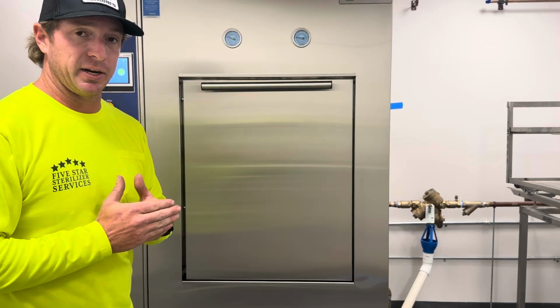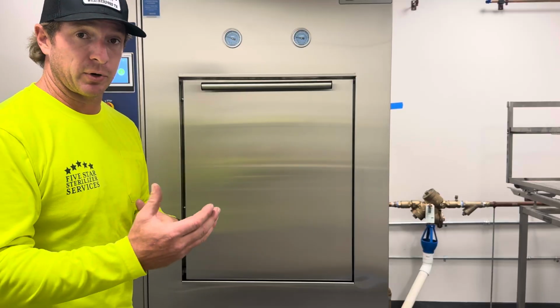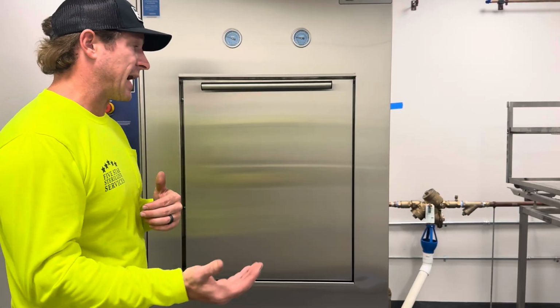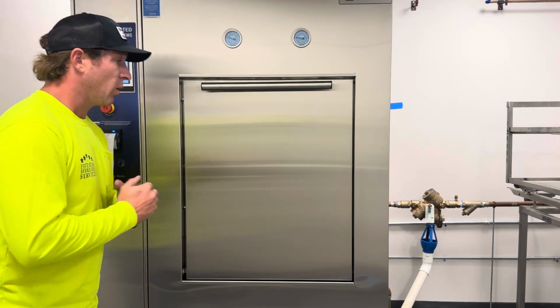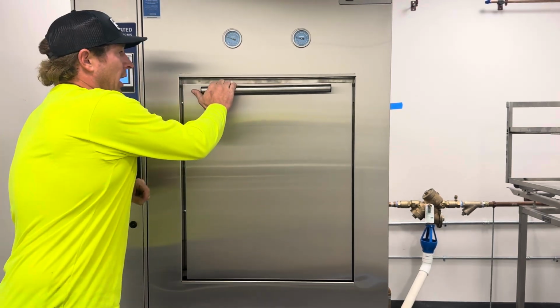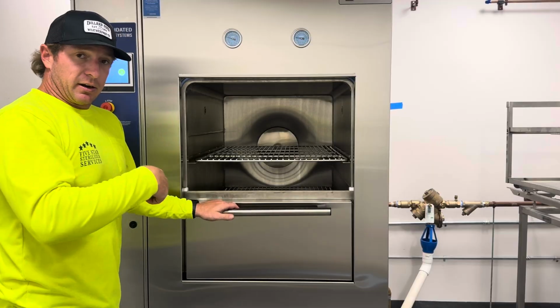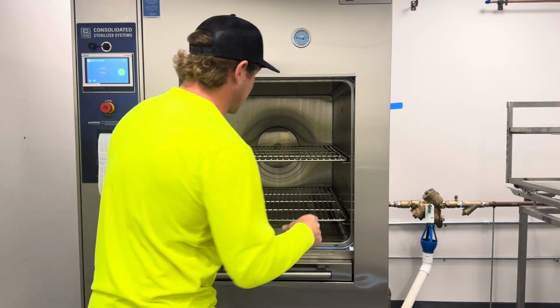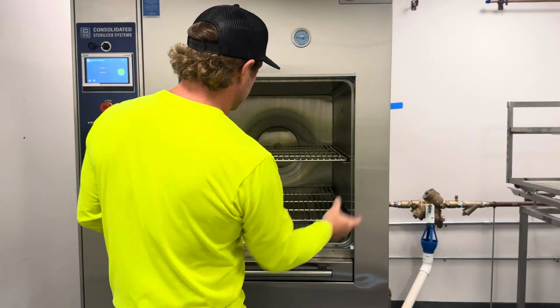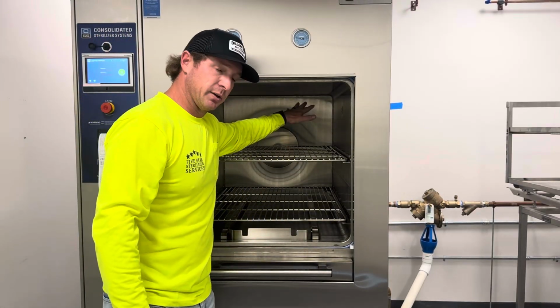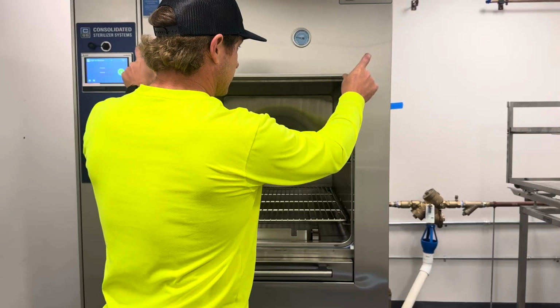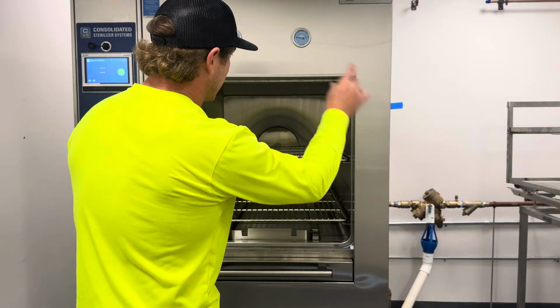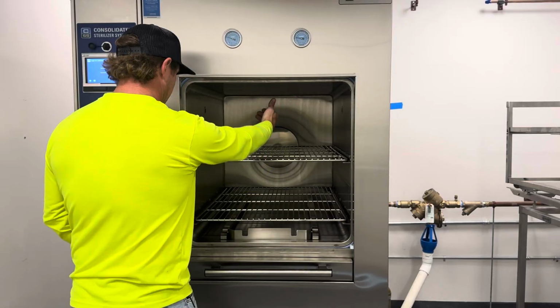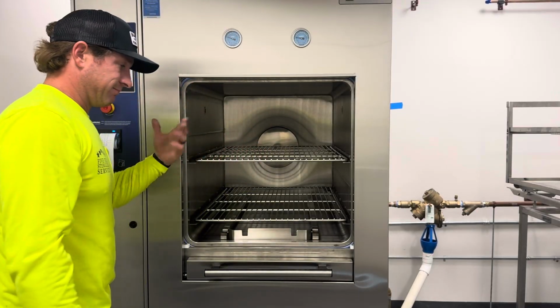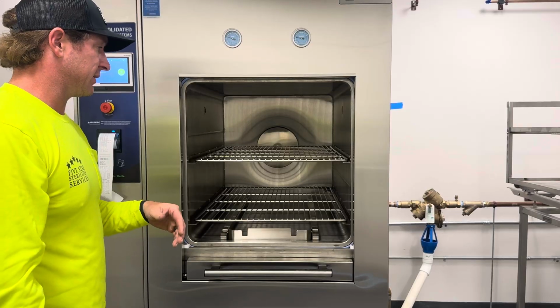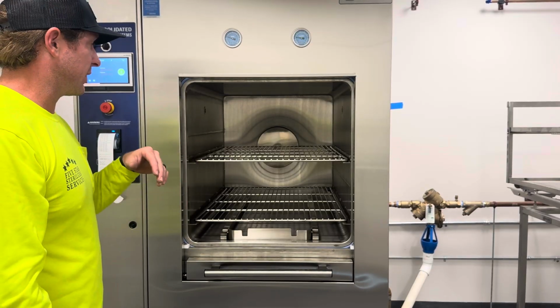We need to allow a little bit of time for the steam generator to build up pressure in the generator, but also the jacket. If you guys do not know what I mean by the jacket, just like you and I wear a jacket to insulate ourselves and keep us warm, there is a thin reservoir all the way around this chamber. This is the chamber where you put your load. There's a reservoir that holds steam all the way around the chamber, all the way back and in the back, and that serves two purposes really.